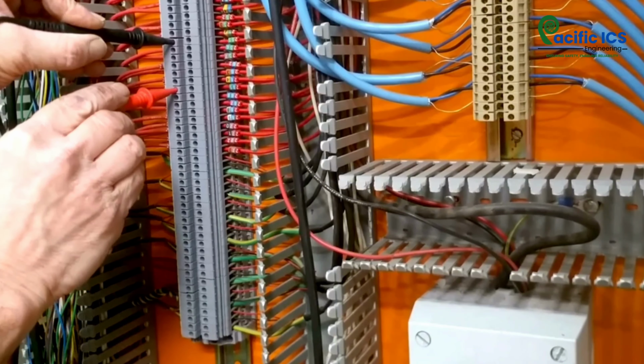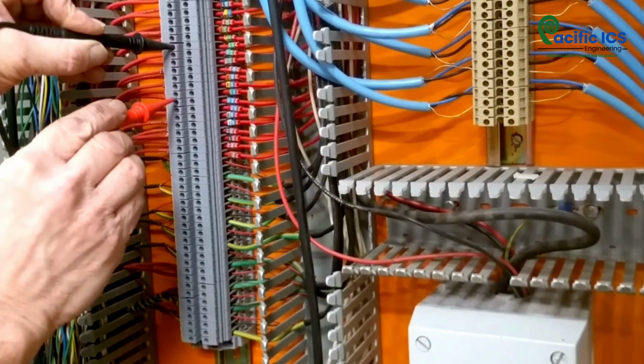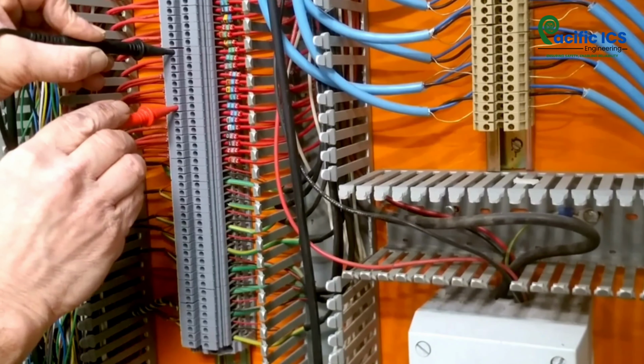FAT, or factory acceptance testing, involves testing the control system logic, panels, instrumentation loops, and interlocks before shipment. It confirms the equipment works as intended per design. We simulate input signals, like triggering high pressure, and confirm the PLC logic closes the valve within 2 seconds. We validate alarms, diagnostics, and fail-safes. You wouldn't fly in a plane that wasn't tested on the ground first. So why trust a safety system that hasn't had a dry run?